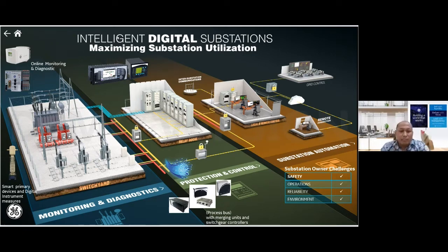So by having this data, engineers or operators can define the maintenance plan to avoid any unplanned outages. The main difference from the conventional substation is also on the side of the connection from the switchyard to the control relay room. As we can see here, in the past there were many cables laid from the switchyard up to the relay panel, so the quantity of cable and the size of the cable trenches were big. Now, with a digital substation, only limited cable needs to be laid from the switchyard up to the control room, because the copper wire from the instrument transformer, for example, up to the control room will be replaced by fiber optic cable, which means the size of the cable trenches can be reduced.